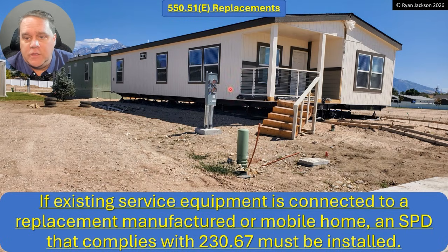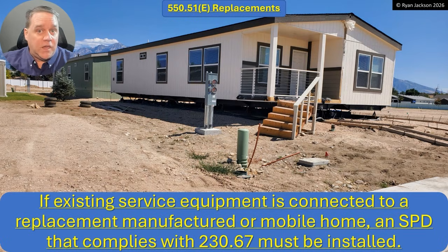A service change would mean that you're changing this equipment. And that's probably not something that happens very often. For a manufactured home, these things are usually dropped in place and they just stay there forever. If it's a mobile home, then they drop them in place and they may stay there for 6 months or 60 years, right? Anywhere in between. And they usually will take it with them if they ever move. So what this rule is saying is if existing service equipment is connected to a replacement manufactured or mobile home, then a surge protection device that complies with 230.67 must be provided.